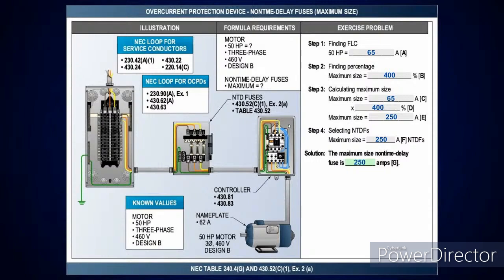But look at this. I've got the same motor here. Now I'm going to look at the maximum, and if I drop down to exception 2, or I'll look at C1B, depending on which one y'all are looking at, you come down, you pick it up, it's going to tell you that if I have non-time delay fuses, I can increase those, and it says shall be permitted to be increased. And listen to what it says, but shall in no case exceed 400%. So it says I can't exceed. That means I've got to do what? Drop down. And that's another percentage that's above the 125%. So if I take the 65 amps at 400%, that's going to give me 250 amps, and you'll need a 250 amp overcurrent protection device.